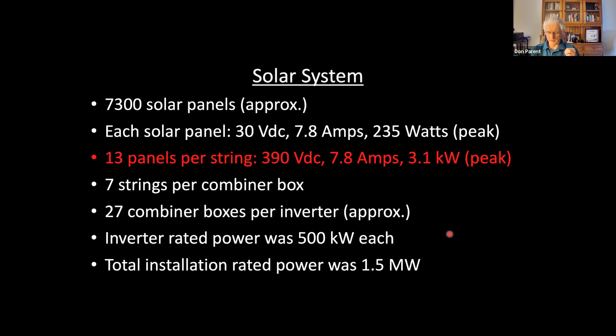So, other things to consider. There are miles and miles of wiring up there. Hurricane Sandy occurred sometime between when the solar panels were installed and when the fire occurred. There were 1,200 hand crimp connections that were made on the roof by somebody with a hand crimp tool and a wire spool. There were mismatched connector types. The installation and custom and practice needed to be evaluated, which we'll look at momentarily. And what was the maintenance and oversight of the system during the period that they actually ran the system?